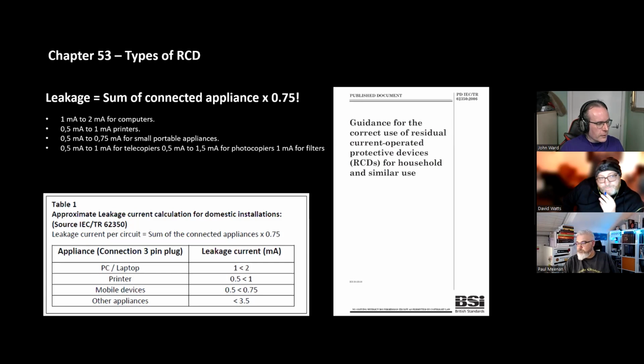Paul Bruton and Nicholas Priest, C3 for a type AC RCD, and the answer is definitely, depending on what it's supplying. But if it's supplying just socket outlets, definitely, because you've got no control over what can be plugged in, and anything that plugs in pretty much is going to have some kind of electronics in it with DC in there, unless it's like ye olde electric fire with the glowing element in the front. But pretty much anything else, yeah. So definitely a minimum of a C3 for that.